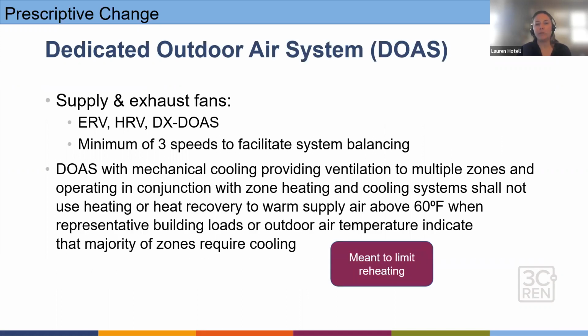Dedicated outdoor air systems are units that are used to filter, condition, or temper air separate from the space conditioning system. The goal of this is to limit reheating of the air, which is one of the requirements. So for dedicated outdoor air systems providing mechanical cooling and ventilation to multiple zones and operating in conjunction with zoned heating, you want to make sure that the supply air does not get warmed above 60 degrees when the building load or the outdoor air temperature indicates that the majority of zones require cooling. This is also meant to help reduce our energy usage.